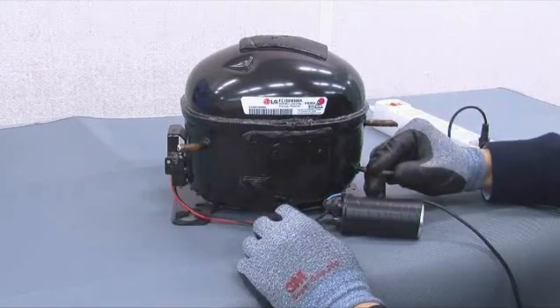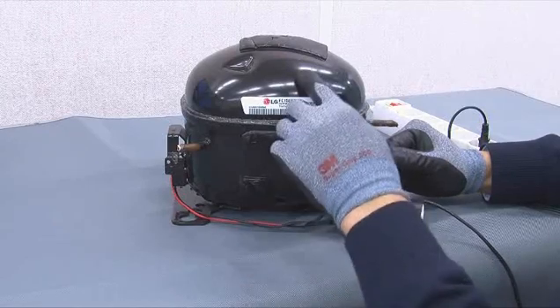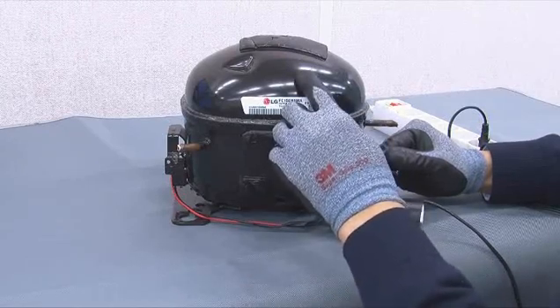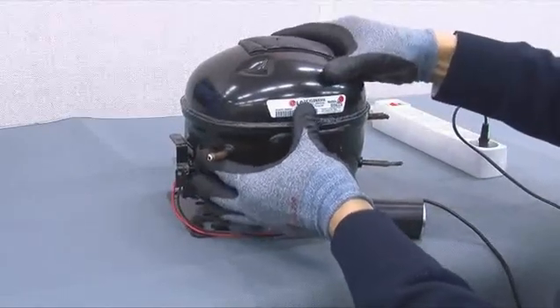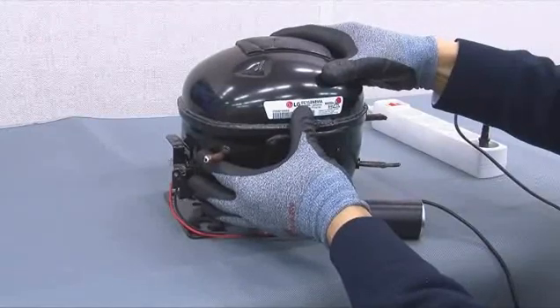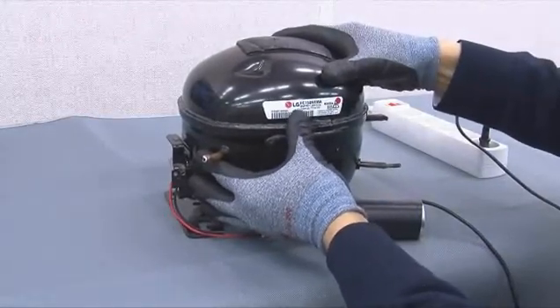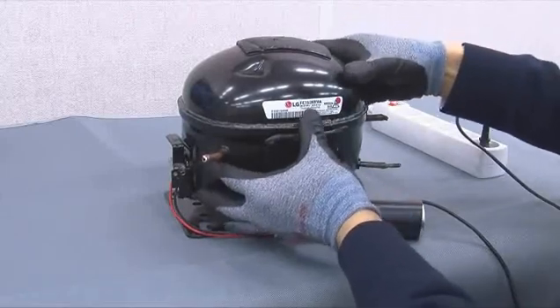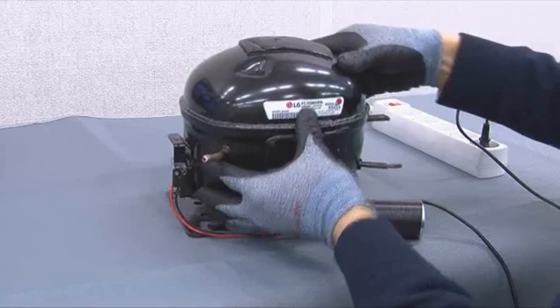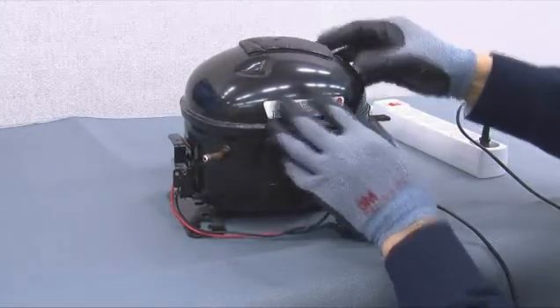If outlet pressure is too weak, it is assumed to be due to the compressor. When the compressor is shaken slightly, the motor inside is also shaken and a bumping noise can be heard. In this case, the inner motor is abnormal.